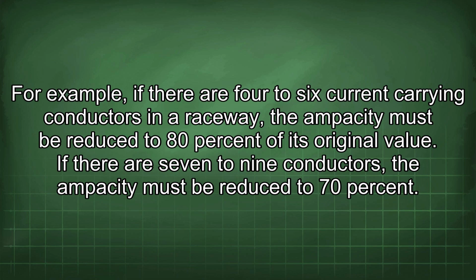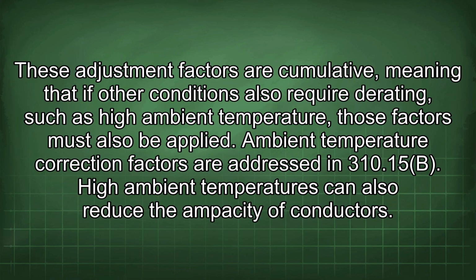For example, if there are 4 to 6 current carrying conductors in a raceway, the ampacity must be reduced to 80% of its original value. If there are 7 to 9 conductors, the ampacity must be reduced to 70%. These adjustment factors are cumulative, meaning that if other conditions also require derating, such as high ambient temperature, those factors must also be applied. Ambient temperature correction factors are addressed in 310.15(B).